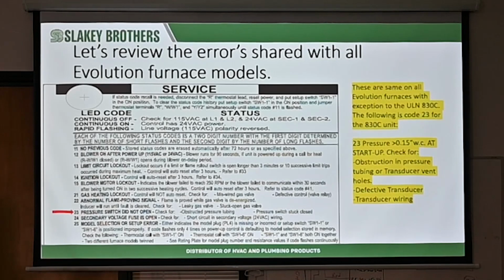After you figure out you've got a bad board or a bad inducer motor, don't forget to turn this off. Because every winter I get a phone call: hey, Juan, remember last week you said we got to replace this inducer motor? Yeah. Well, dude, now it's giving me this fault code. I'm like, did you change the model chip? I didn't change that. Okay, then go look at your dip switch number 6.